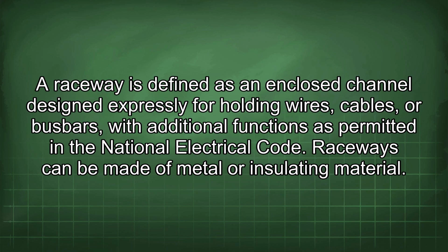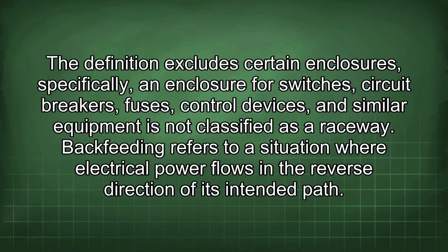A raceway is defined as an enclosed channel designed expressly for holding wires, cables, or busbars, with additional functions as permitted in the National Electrical Code. Raceways can be made of metal or insulating material.